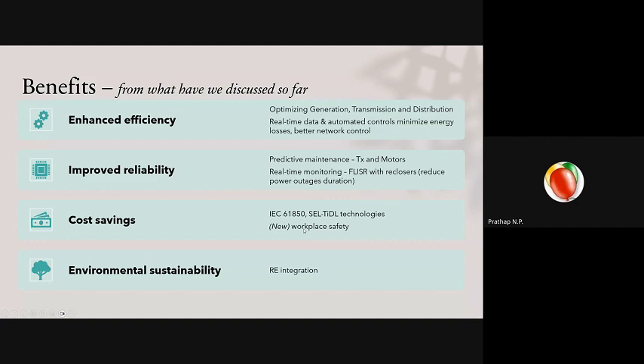Just a fun fact, since we were talking about layers and the OSI model: in IEC 61850 there are two protocols called GOOSE and Sampled Values. These are high-speed protocols—not like the 1 or 2 seconds you see in SCADA. In the SCADA world, protocols like Modbus and DNP transmit with a delay of about 1 second or half a second, which is very slow for the protection world. In my domain, where you send trip and close signals, all of that has to happen instantly.